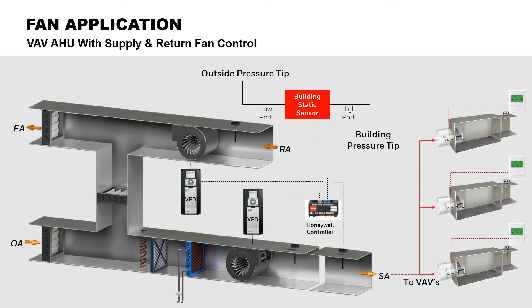One of the most common uses of a VFD is in air handling units and variable air volume boxes, or VAV boxes. In this example, there is an air handling unit with a supply and return fan. Both fans are modulated by a VFD. The air handling unit and the VAV boxes each have a DDC controller. The AHU controller commands the VFDs to the desired fan speed. For the supply fan, the VFD maintains a duct static pressure set point established by the test and balance contractor.